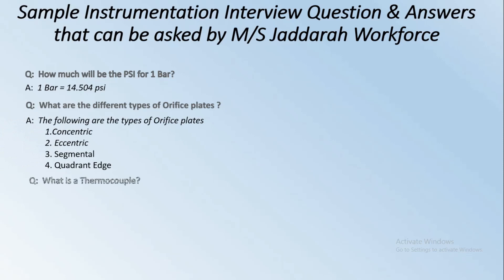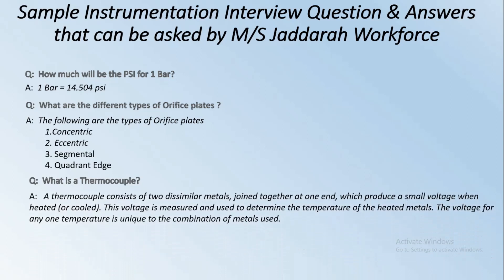Next: What is a thermocouple? A thermocouple consists of two dissimilar metals joined together at one end, which produce a small voltage when heated or cooled. This voltage is measured and used to determine the temperature of the heated metals. The voltage for any one temperature is unique to the combination of metals used.